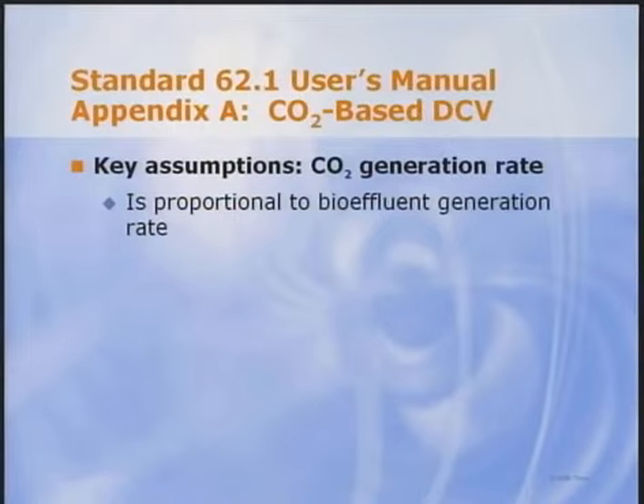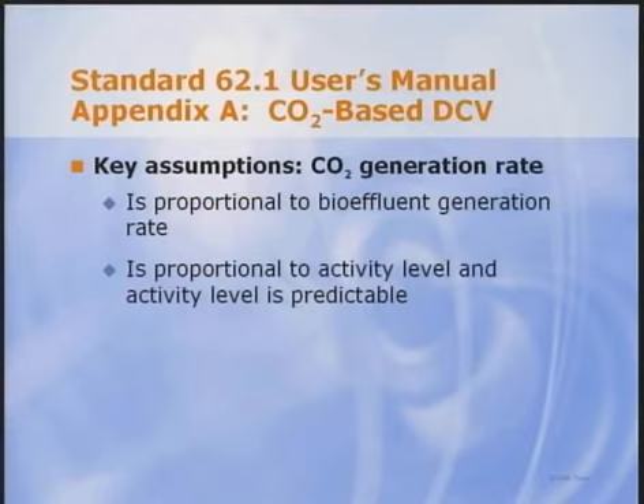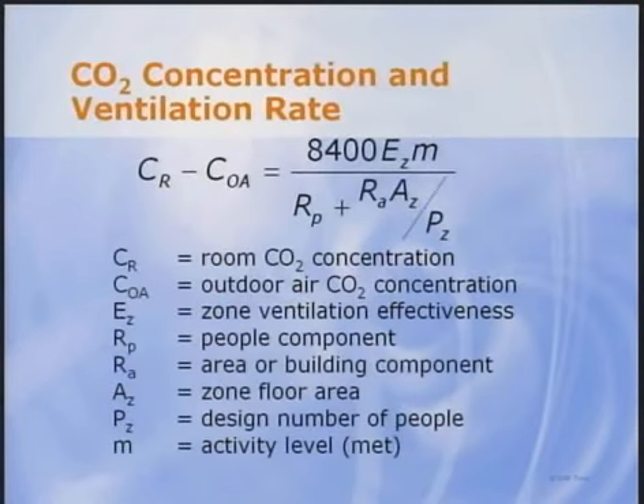They are the fundamental reason why Standard 62 includes an occupant component to the space ventilation rate. The second assumption is that CO2 and bioeffluents are generated at a rate proportional to activity level in a known manner, and that activity level can be reasonably predicted for a space in question. While there is research that supports both of these assumptions, there is nevertheless some uncertainty. I will discuss later a new research project currently being developed by ASHRAE that will be looking into this issue further. Here is the CO2 equation once again.